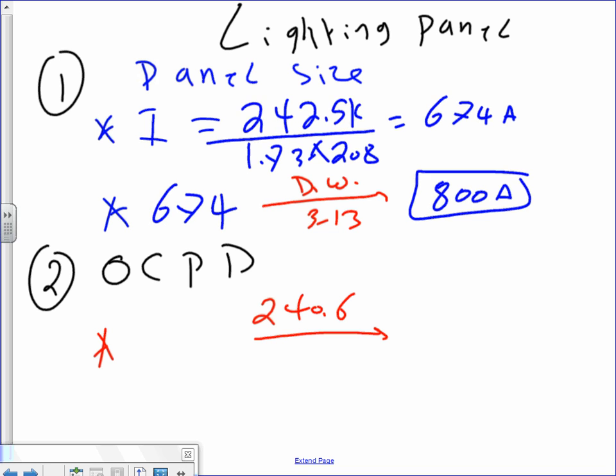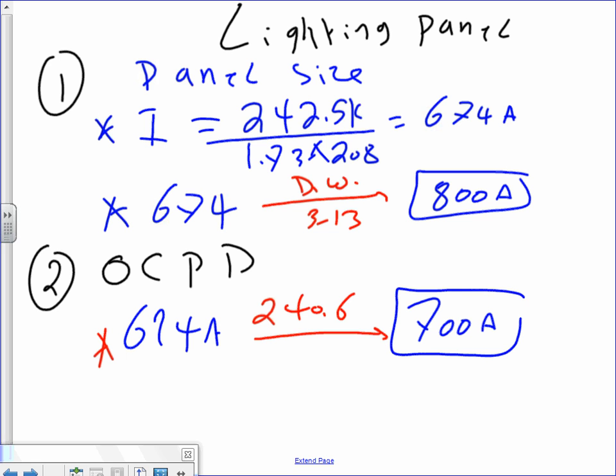800 amp panel. Okay, overcurrent protection device, same thing, 674 amps. That will get you 700 amps. Can you guys see the difference? Now I have an 800 amp panel protected by a 700 amp circuit breaker. Is this okay? Yeah, no problem. Brandon is an engineer. He said, you know what, Chad, I want to up the overcurrent protection device to 800 amp, match it to the panel, and size everything for 800. That's okay. But for the process, this is how you guys go. Size it, 700. Okay, cool, good.